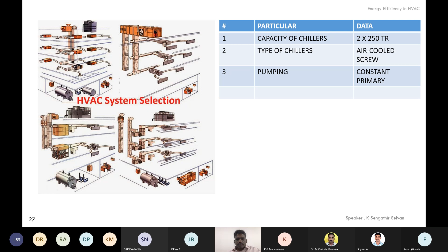The fifth energy conservation point is that we have chillers working in VFD mode. Even in air-cooled chillers, the compressors can be fitted with variable speed drives, and the condenser fans also can be provided with variable speed drives. Why do we need VFD, and how does it justify this inclusion? Mainly because the entire air conditioning equipment is selected for the peak load that occurs either 0.1% of the time or 4% of the time. I have designed a system for say 500 TR, but my average load will be around 300 TR only.